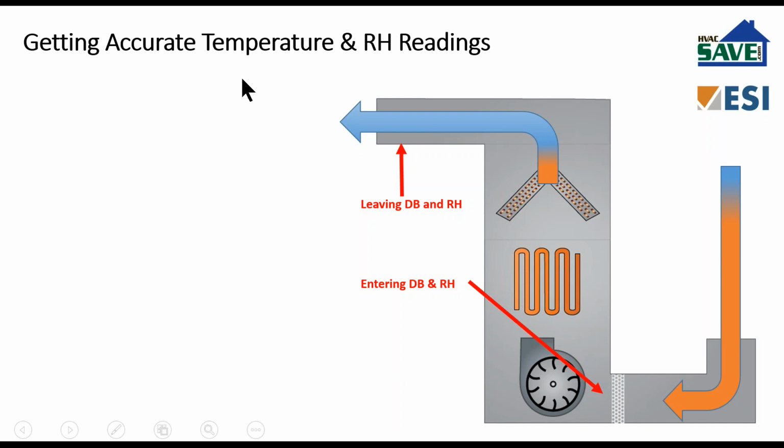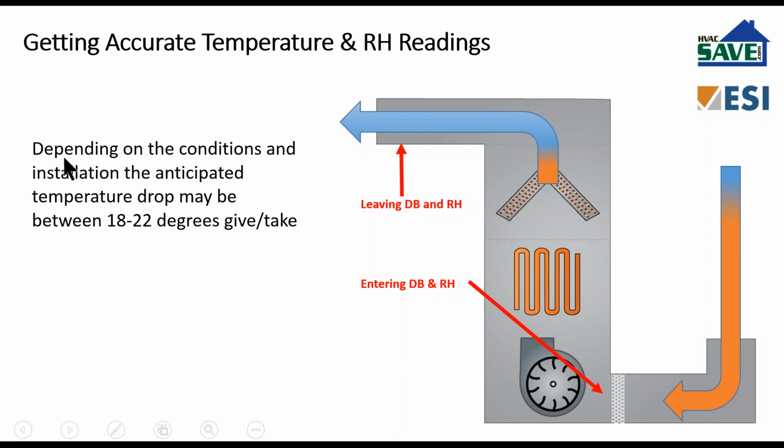Okay, more on temperature and relative humidity readings. Depending upon the conditions, the ambient conditions and also the installation conditions, the anticipated or expected temperature drop may be between 18 to 22 degrees, give or take. This does not necessarily come from us. This comes from your OEM, so be sure to refer back to them, okay? But that's a rule of thumb that we hear.